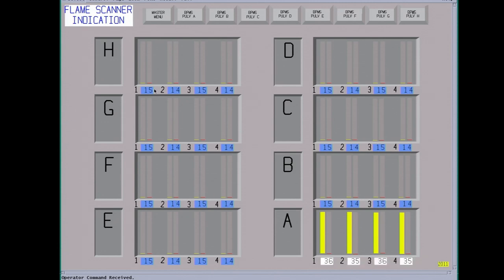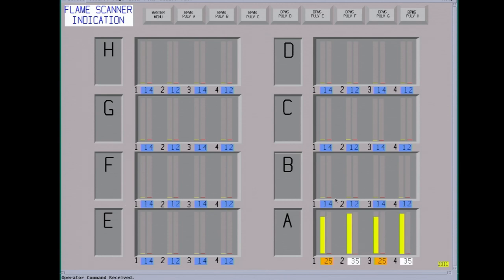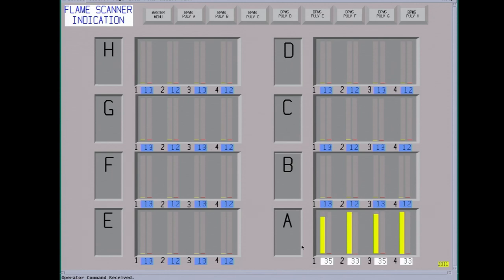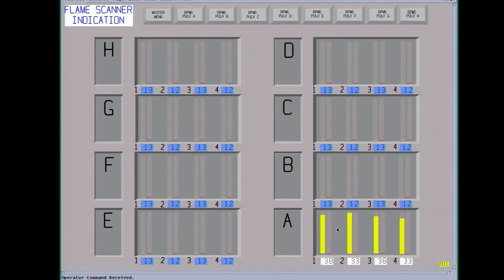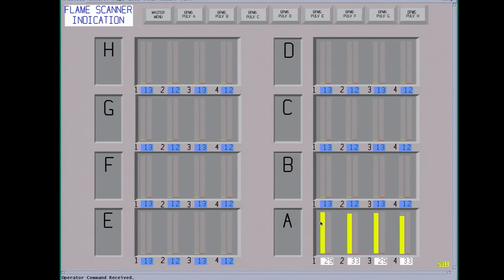All the sleeve dampers went to cool down. This is just providing a little bit of air through to cool down the burners. It's another reason why the O2 is so low when you start up. You have to have the cooling air go through. So at this point, we have four igniters running on one deck. Before we can start burning coal, we have to have the precipitator in service. Like I said, the dry sorbent injection removing any sulfur, and the mercury removal using activated carbon has to be in service.